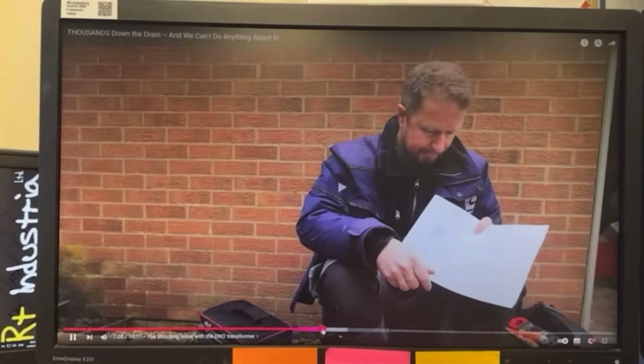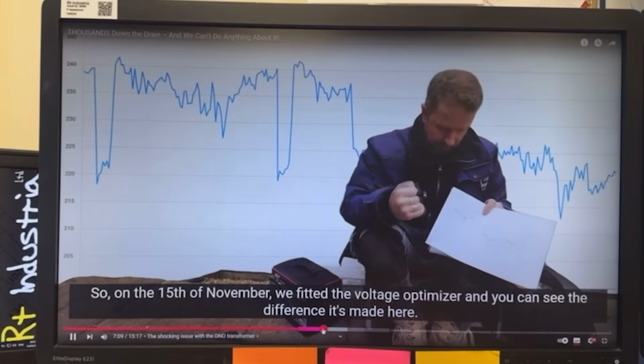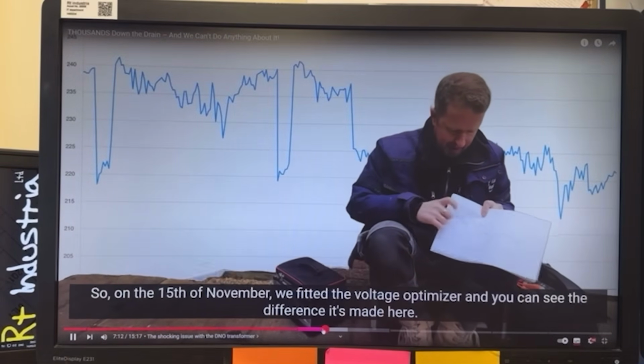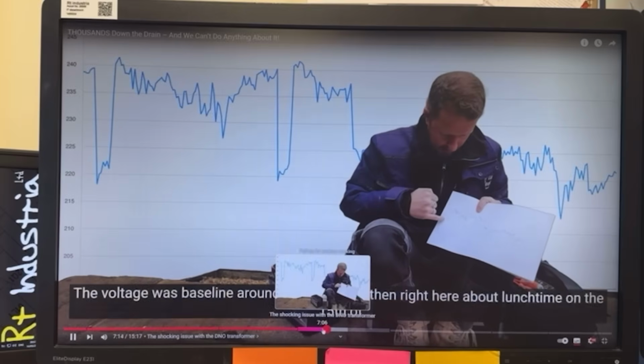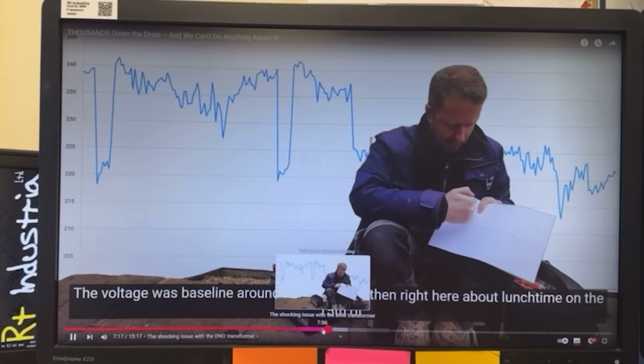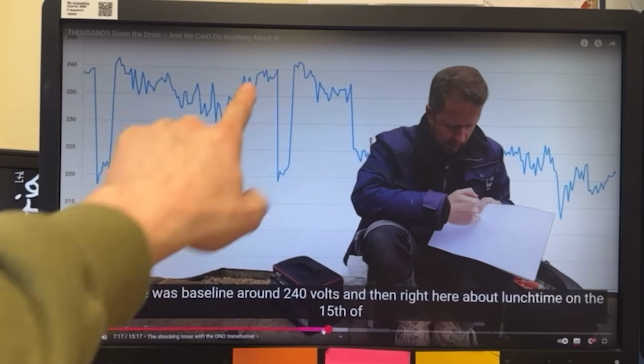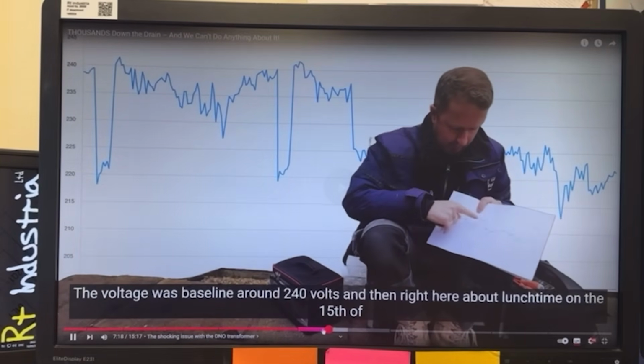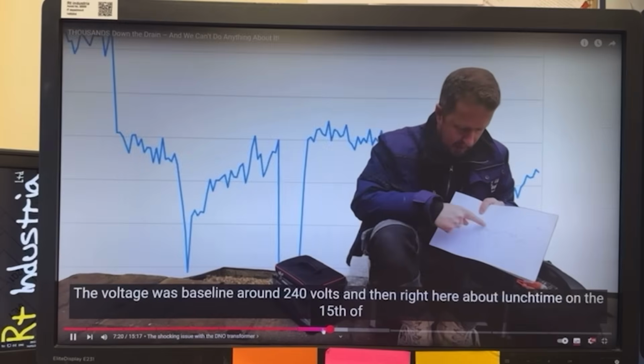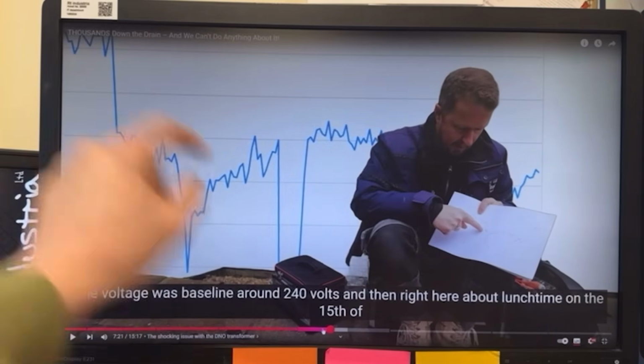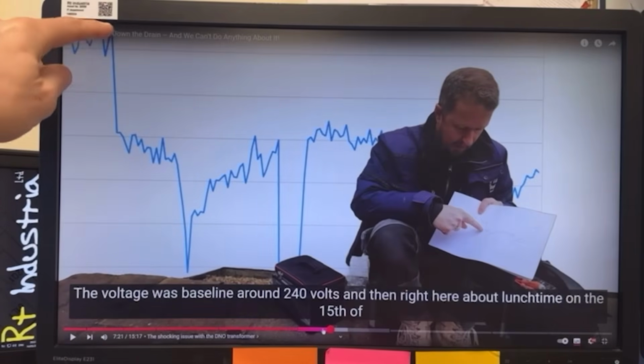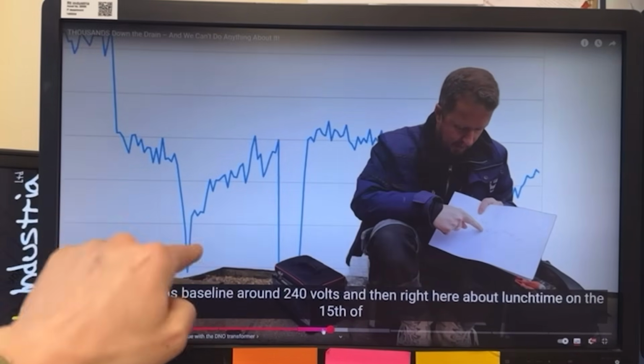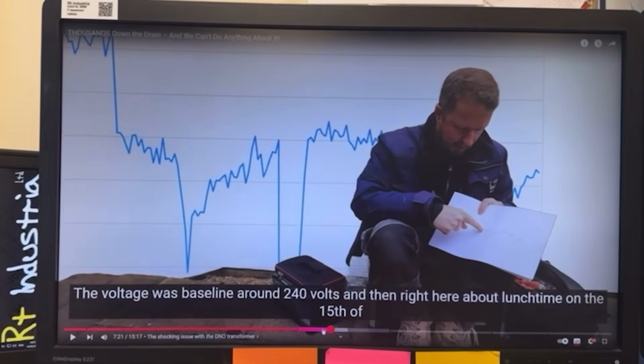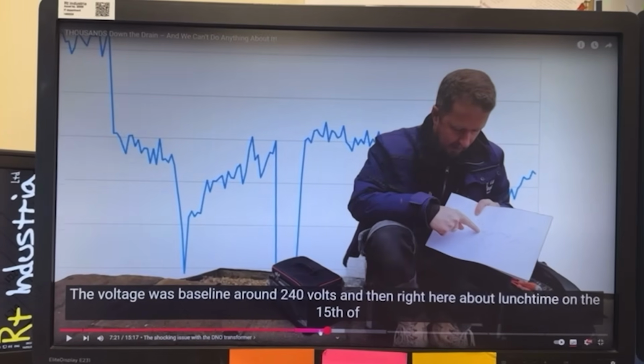So on the 15th of November we fitted the voltage optimizer, and you can see the difference it's made here. This was the 14th of November, the voltage was baseline around 240 volts. Note this shape, this is the shape for the day. Then right here about lunchtime on the 15th of November, it's the same shape, but it's dropped by this much. The voltage optimizer is just taking this level here and dropping it down to this level here. Same pattern, same problems, but at a lesser voltage, which really doesn't solve anything.